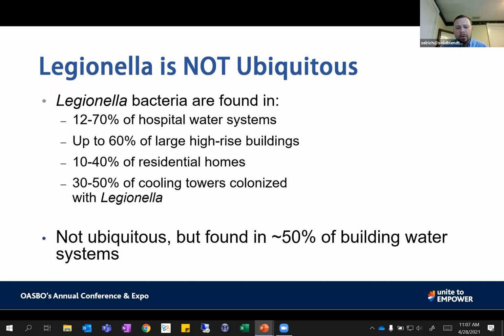If you've got cooling towers, 30 to 50% of them have the bacteria. That can be easily rectified by following a water treatment program that coincides with ASHRAE's recommendations, cleaning your tower, having proper biocides in place, and feeding it properly. So in general, it's not found everywhere, but it's found in about 50% of building water systems and commercial cooling towers.